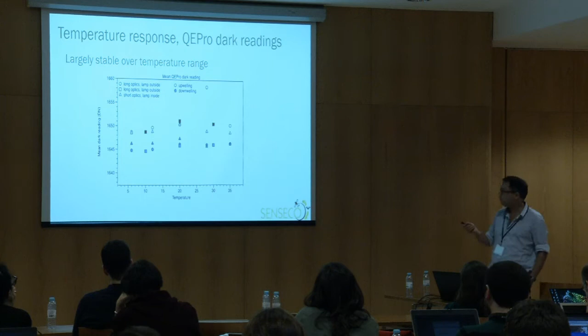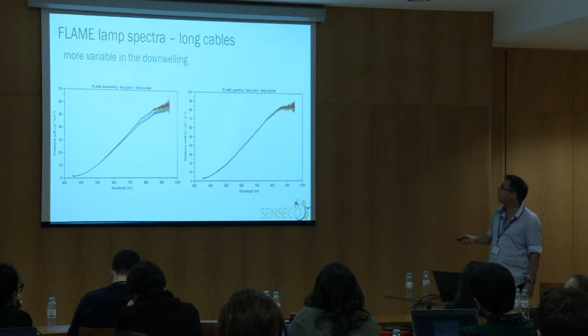All right. So just the standard deviations across, also like I said, at each point we measured 90 times, so we can look at how variable it is between consecutive scans. This is the standard deviation of that. There's no really strong apparent response to temperature in terms of the inherent variability of the system. Maybe something there, but overall, nothing really strong. It's more dependent on the actual wavelength itself, particularly with the flame here, and it gets very noisy at that end of the spectrum.